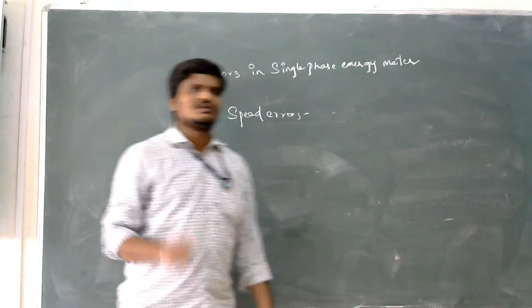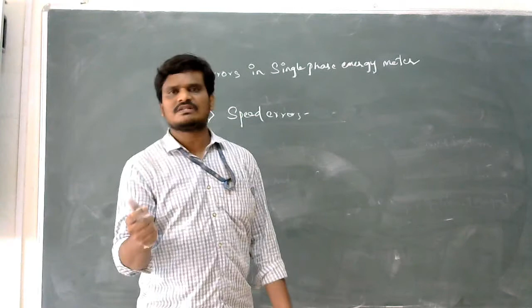Or else, if the rotation of the disc is very slow at a particular interval of time, then also the registering or counter mechanism will give a wrong reading. Why? Because the rotation of the disc should be uniform in a particular interval of time. It should not be fast or slow. So how is the speed error caused in a single phase energy meter? Due to the rotation of the disc being very fast or slow in a particular interval of time.